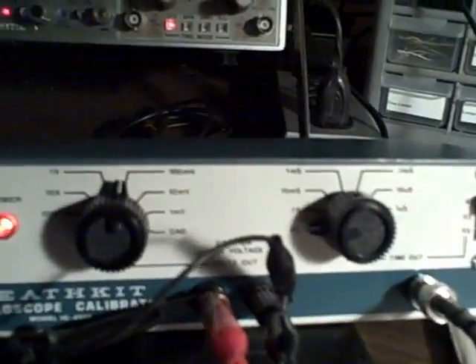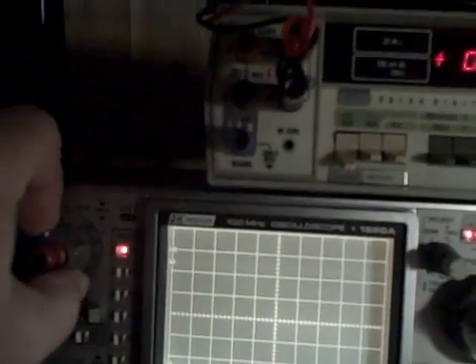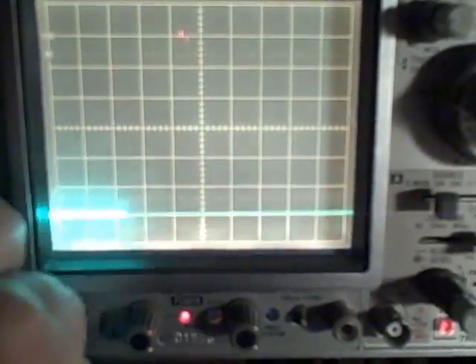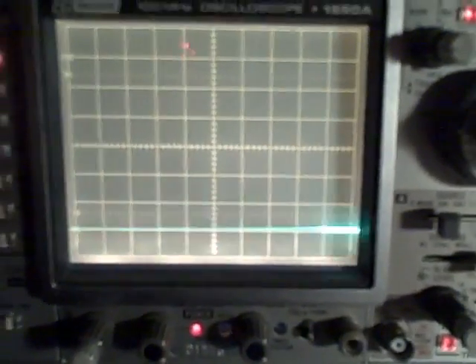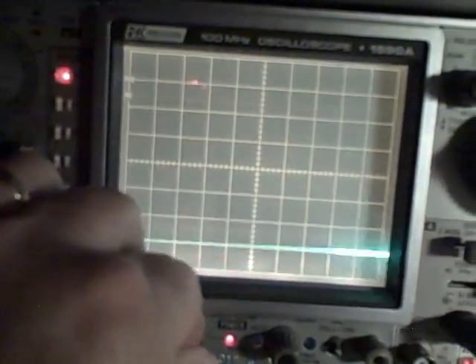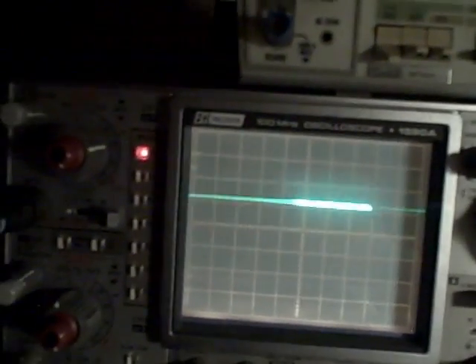And the next range is 100 millivolts. Okay, if I was 100 millivolts, and I'm on the 100 millivolt range times 1 on my probe, then I'm going to go up 1 division. And I just did. See if I can cut down on my... yeah, that's a little easier to see. If I go to the 50 millivolt per division, I should go 2 divisions. 20 millivolts, I should go 5 divisions. No problem. Let's go to the 10 millivolt setting on the calibrator.